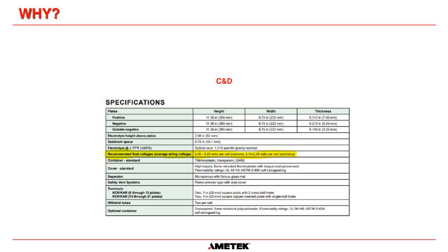A general rule is 72 hours. And once again, if you do it for longer on a vented cell, all it is going to do is boil off more water. It's really not going to affect the cell too much. But you do have to wait until you get to current stabilization before you start the equalized timer. So if the manufacturer's manual says that you should equalize the battery for 72 hours, that is 72 hours after you get to current stabilization. And if you have a huge battery, it could take up to 24 hours to get to current stabilization. So that means you would need to perform the equalize actually for 96 hours.